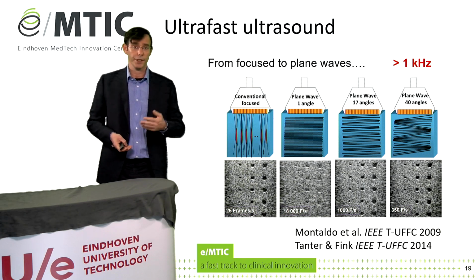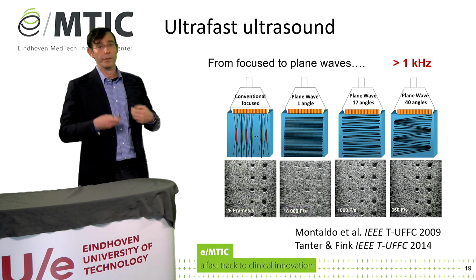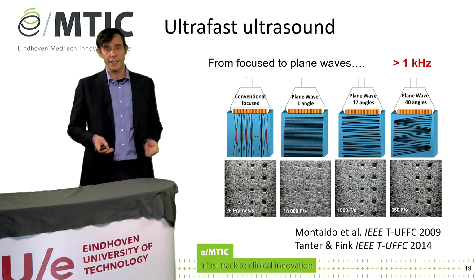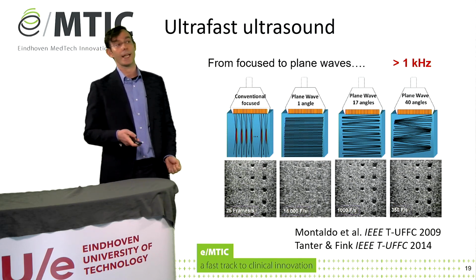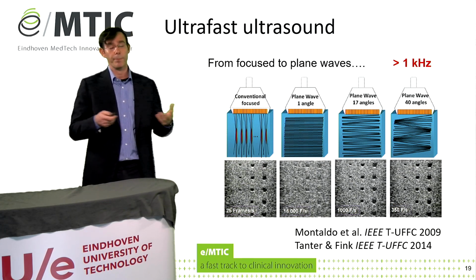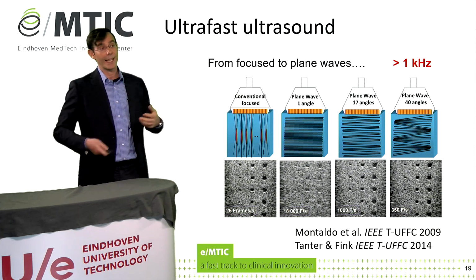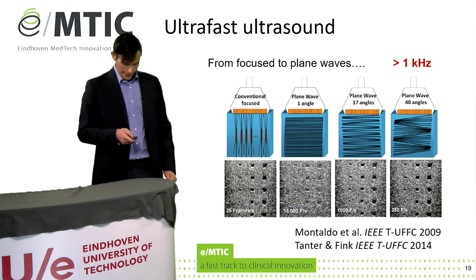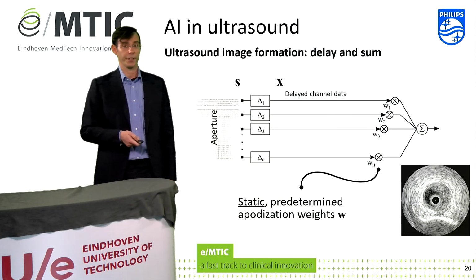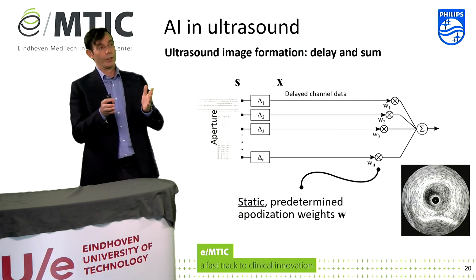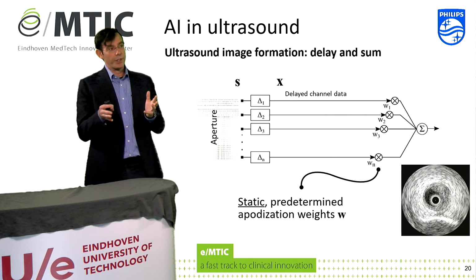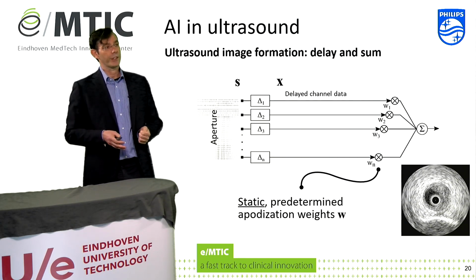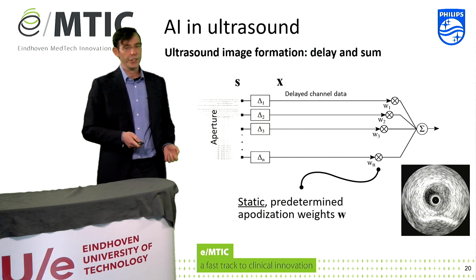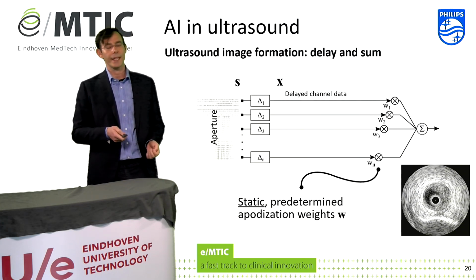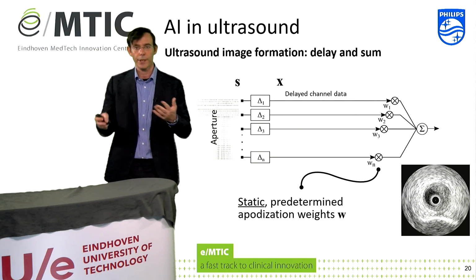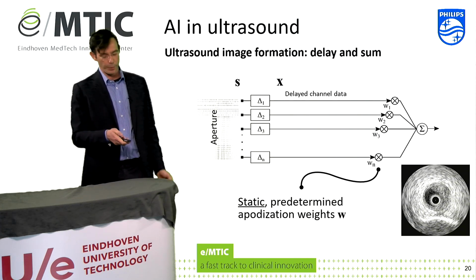But with very high quality nowadays, you can achieve frame rates of above 1 kHz, which is really exceptional and far beyond any other imaging modalities. And this has also opened many possibilities for other modalities that you will see in the following part of this presentation. Going back to the way the image is formed, basically this is based on delay and sum. So you receive the echoes back, you apply some delays, and you sum them with weights in order to get rid of some artifacts, and this is called apodization.